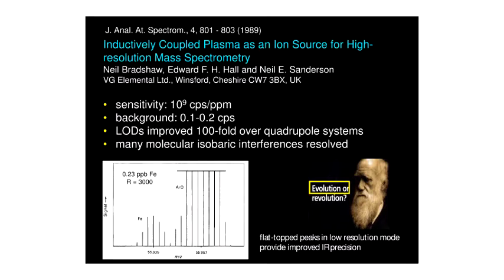This is an evolutionary process, but equally important: with a high-resolution instrument operated in low-resolution mode, you can get flat-topped peaks, meaning any small instability in the magnet still keeps you on the peak. This allows very high-precision isotope ratio measurements. Moreover, the sensitivity of these devices — due to enhanced transmission efficiency and very low vacuum — increased by two to three orders of magnitude over a quadrupole-based device, and very low background gives limits of detection improved 100-fold.